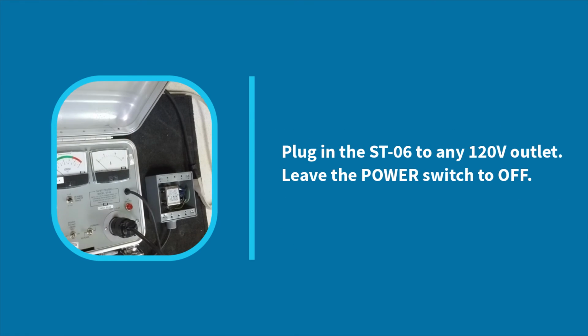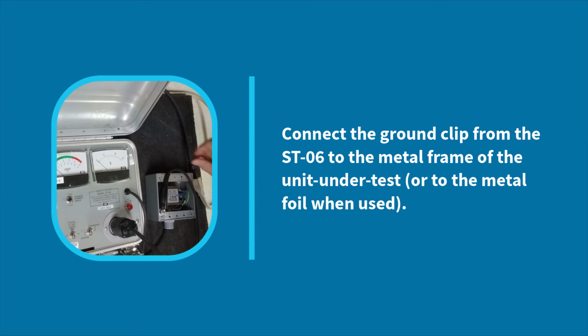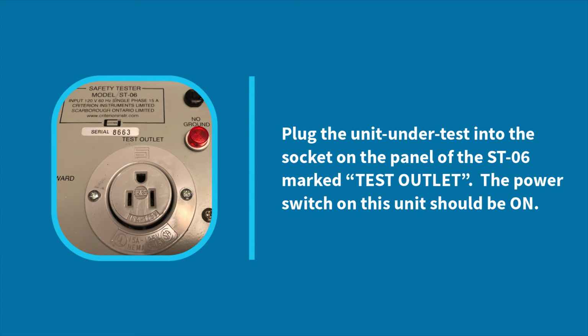Plug in the ST06 to any 120 volt outlet, leave the power switch to off. Connect the ground clip from the ST06 to the metal frame of the unit under test, or to the metal foil when used. Plug in the unit under test into the socket on the panel of the ST06 marked Test Outlet. The power switch on this unit should be on.